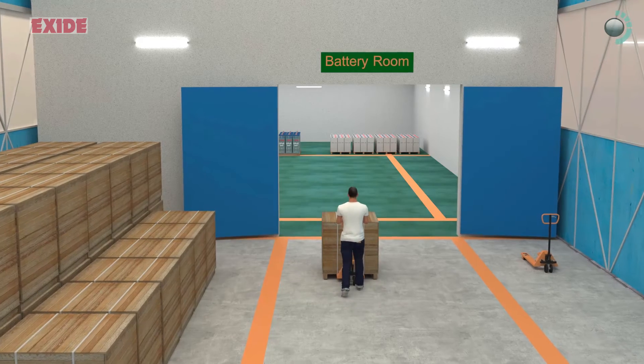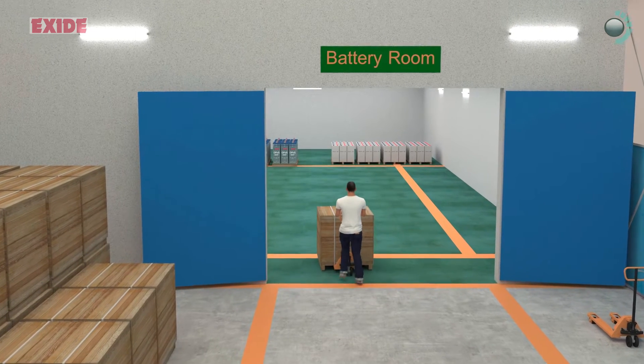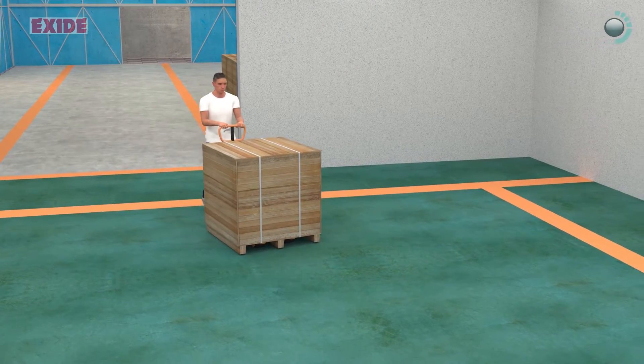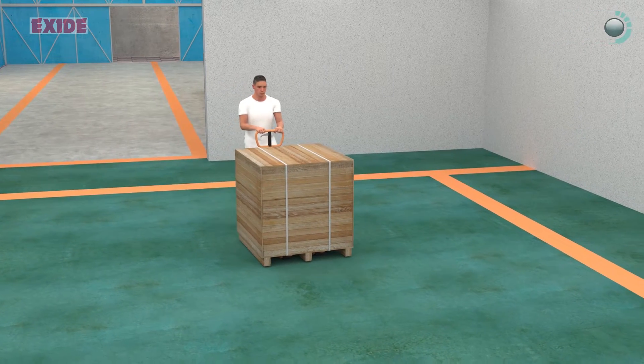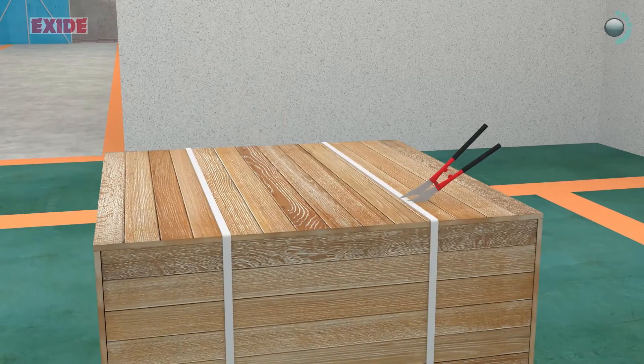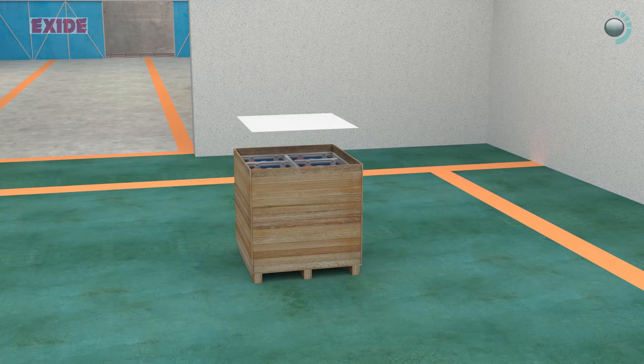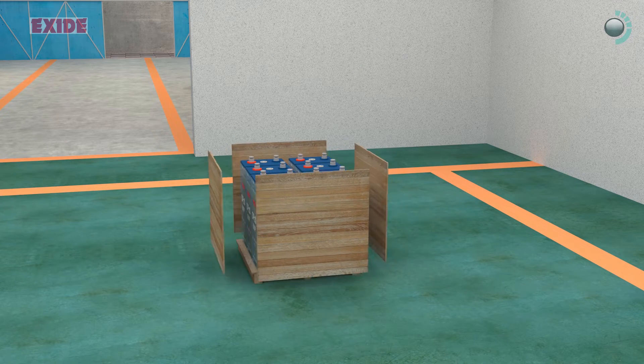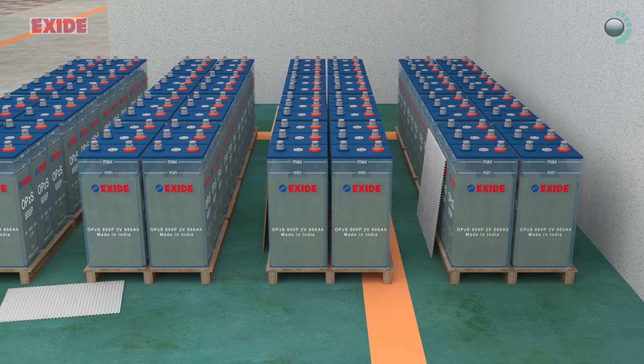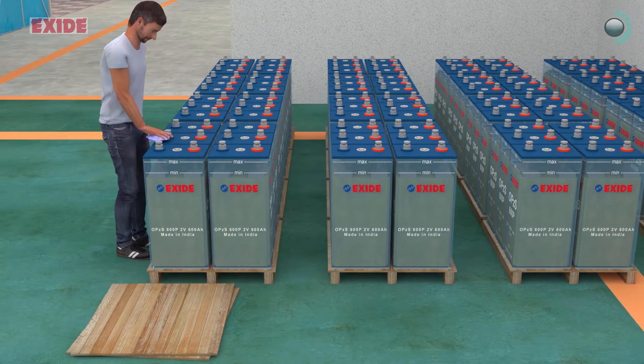For installation of the batteries, carry the batteries with all accessories near the battery room using forklifts or convenient mechanical devices. Then use pallet trucks to take them inside the battery room. After cutting the metal strap, remove the stretch-wrapped plastic using a sharp knife and then remove the thermo-col and hard-board cover. Inspect the module tops for any mechanical damage or discrepancy, and carefully clean off the dust and packing material deposits from each unit and accessory with clear soft cloth.